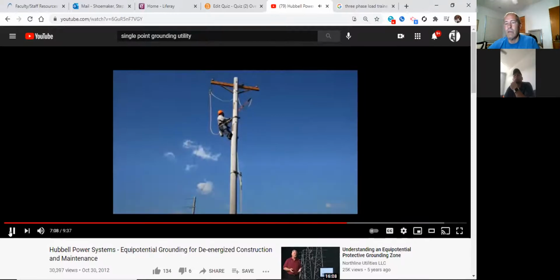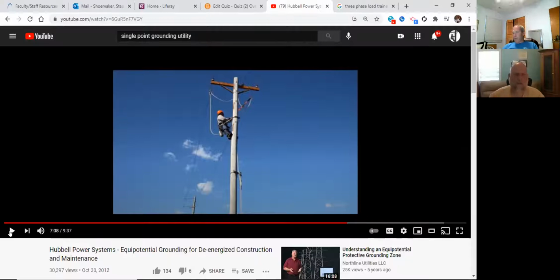He repeats the procedure. Okay, so Professor V, this was not a practice at Santee Cooper. We used what they called single point grounding. Right. He's getting ready to install another set of grounds, what they call dual point grounding. What did you do? We did that. We actually did the closed grounding like that. So you're able to work inside a zone between the two sets of grounds. That's correct. Most of the time that was the practice, until at some point they would allow us to do single point grounding.